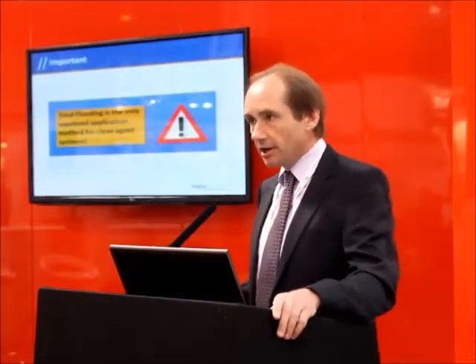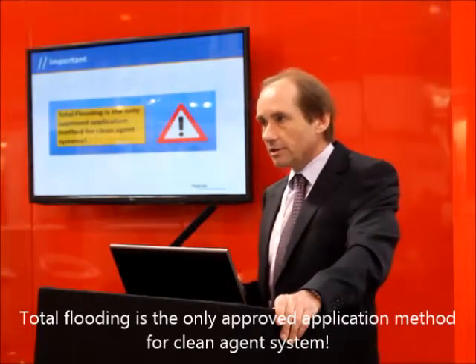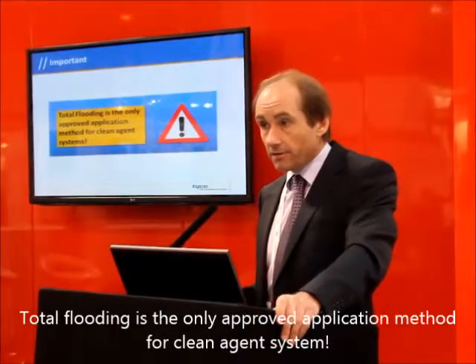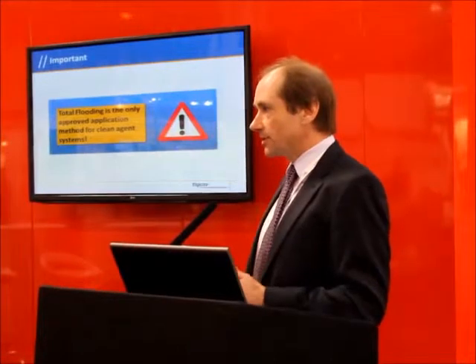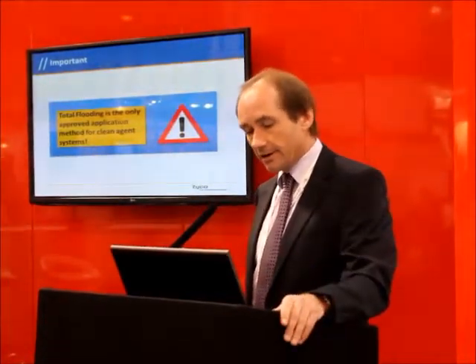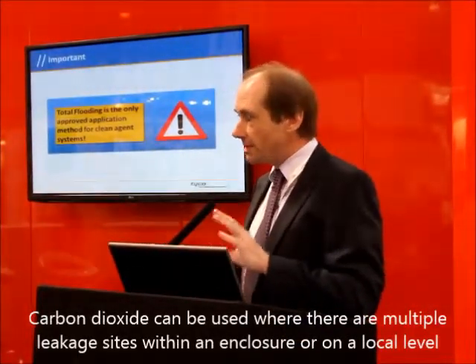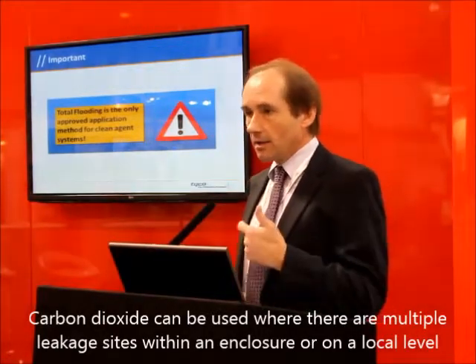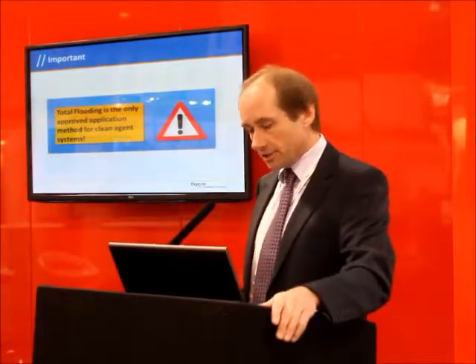When we talk about clean agent systems, we're actually talking about the application of a gas in a total flooding environment. Total flooding is defined by an enclosure that has limited leakage sites from which the gas can escape. CO2, as that second category, may be designed for local application of enclosures where there are more leakage sites than can be tolerated with a typical clean agent system.